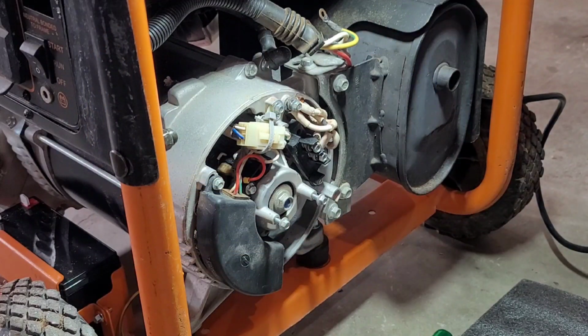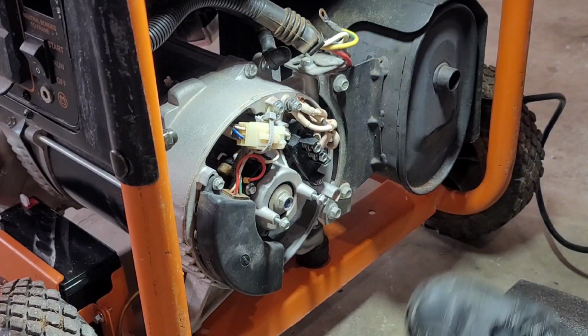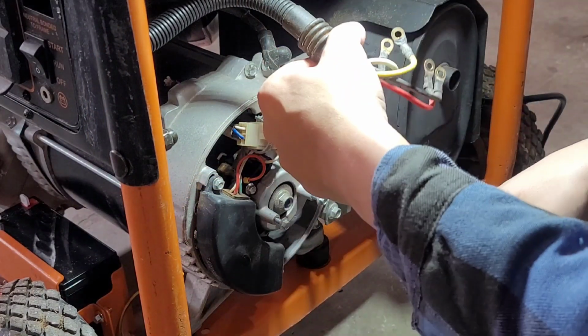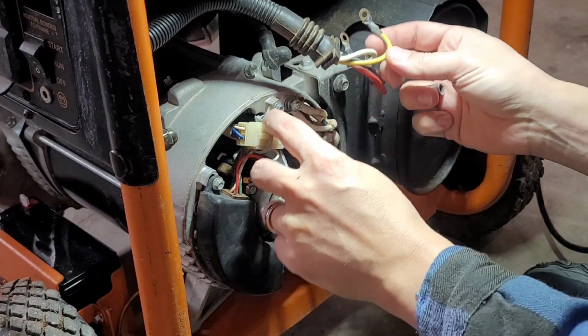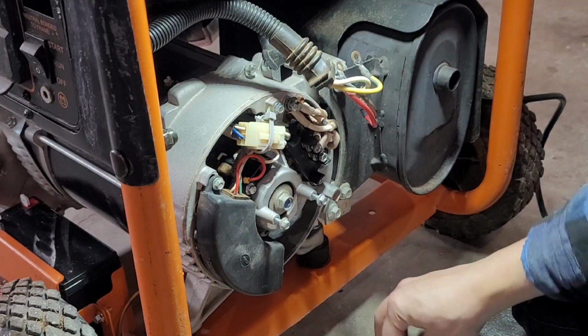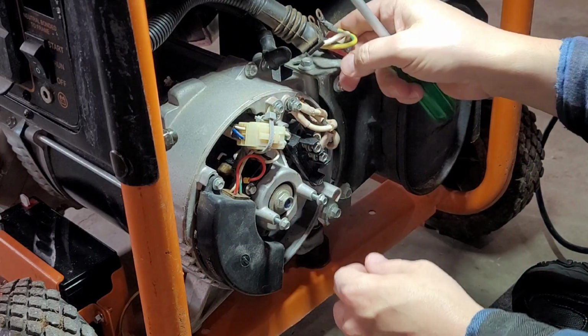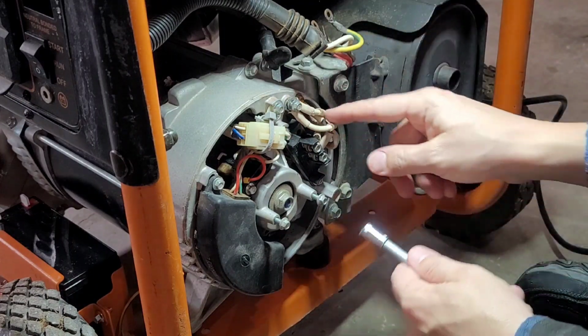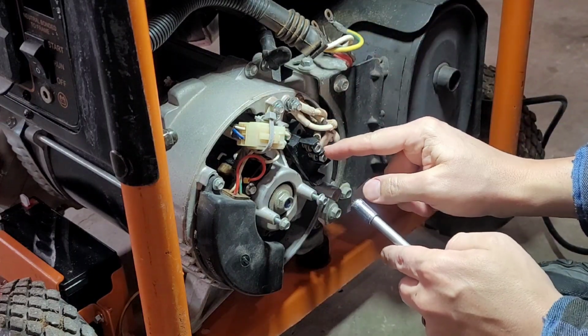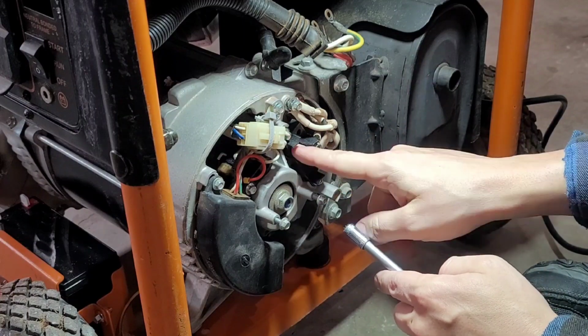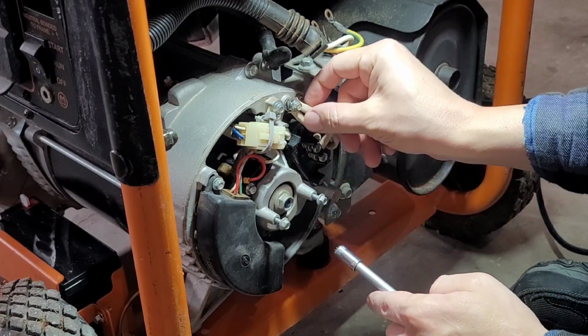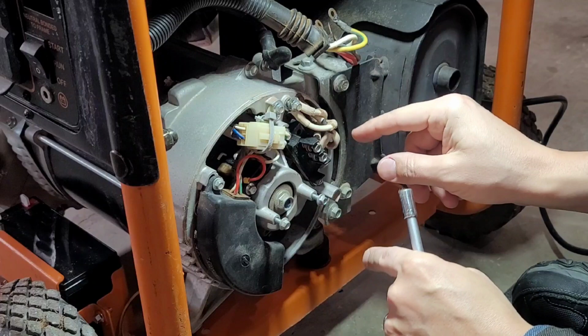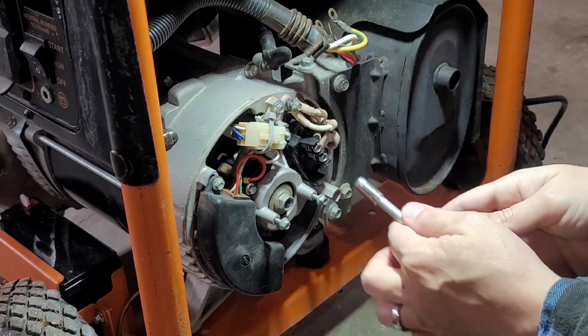All right, now let me get myself set up here. What we're going to do is reinstall the main windings, and it'll be important to make sure we put everything back together correctly. So what we have here are the two hot wires on this insulating terminal block, and we have the two neutrals. There are two windings in there, so this is the common point.